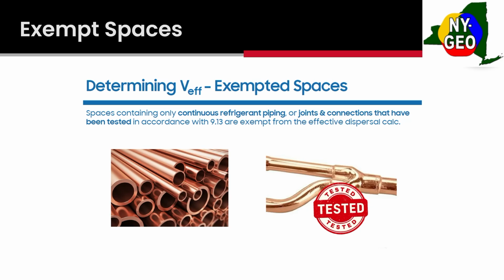It is an exempt space. Or a lot of times you might find continuous runs of refrigerant pipe in a mechanical room. You don't need to worry about refrigerant leaking into that mechanical room. And the big thing I would suggest to contractors is instead of using hard pipe, maybe consider line sets, using soft copper. They come in reels of up to, I think, 167 feet. So that'd be a way to avoid additional refrigerant detection mitigation actions. The big thing using soft copper, you don't want to see spaghetti noodles up the ceiling, so make sure you use enough clamps and hooks to make sure it is properly installed.